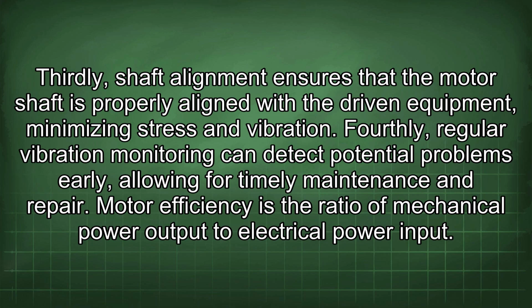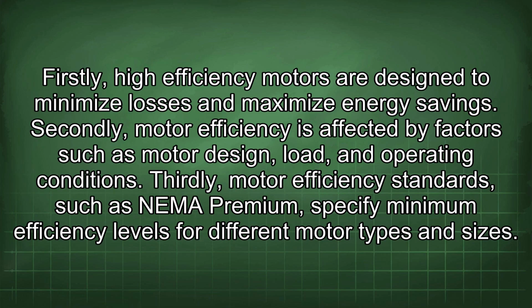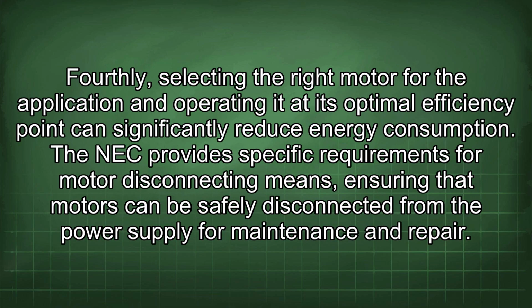Motor efficiency is the ratio of mechanical power output to electrical power input. Firstly, high-efficiency motors are designed to minimize losses and maximize energy savings. Secondly, motor efficiency is affected by factors such as motor design, load, and operating conditions. Thirdly, motor efficiency standards, such as NEMA Premium, specify minimum efficiency levels for different motor types and sizes.